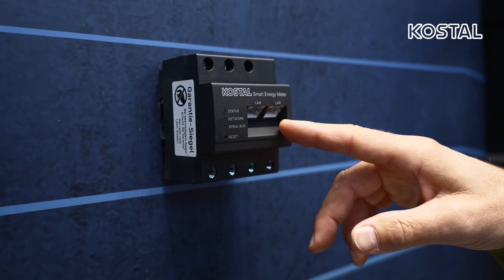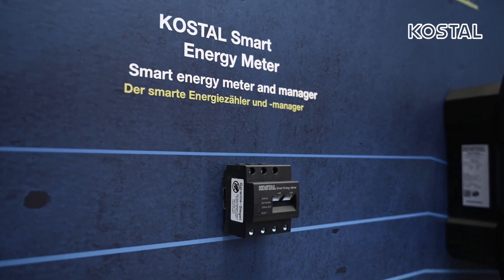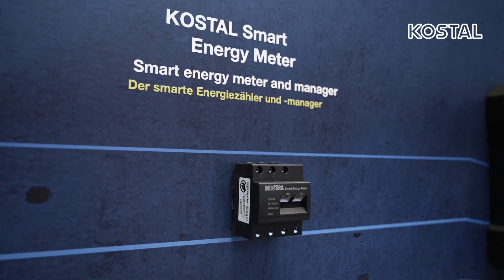The main product features include two LAN and two RS-485 interfaces. The pre-configured RS-485 interfaces allow for simplified commissioning. The KSEM includes integrated three-phase energy measurement up to 63 amperes. Active and reactive power, apparent power, current strength, and power factor are measured for each phase for high safety and maximum accuracy. An optional converter measurement is also possible, along with intelligent control with swarm interconnection.